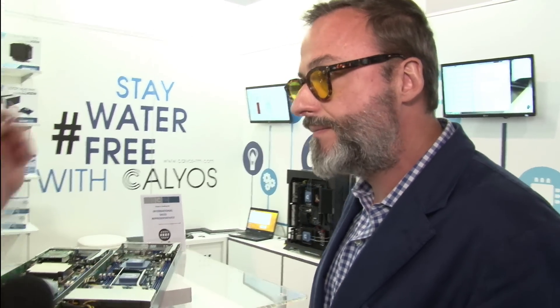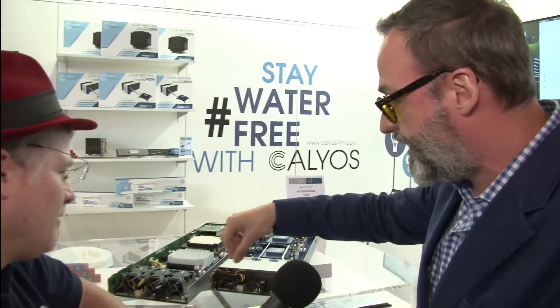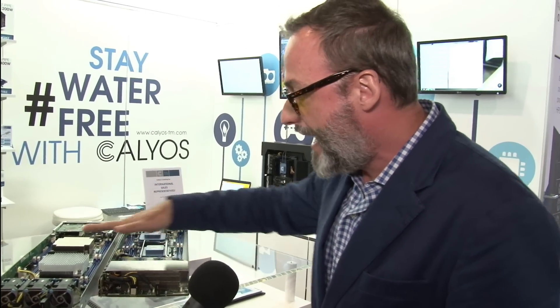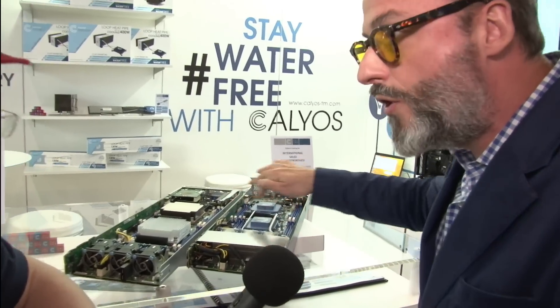Wow, that's an enormous potential saving working with the air at 35 degrees. So how are you moving the heat? Is it through this heat pipe? Are you using vapor? We are using vapor — vaporizing and condensating, and coming back. So it's a completely passive system, as simple as a heat sink, with a delocalization of the problem, and as powerful as a water loop, but water-free.